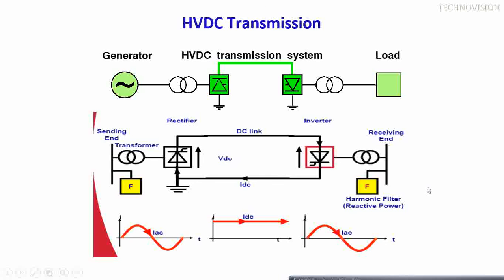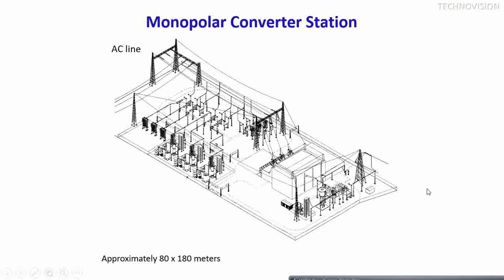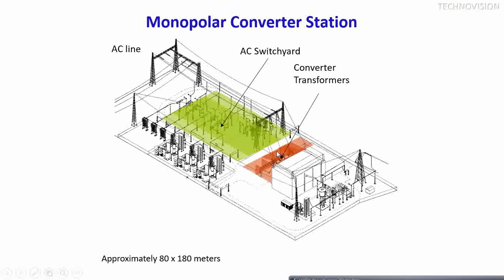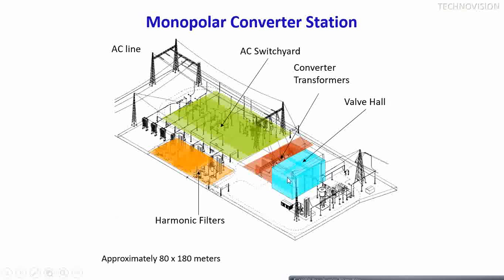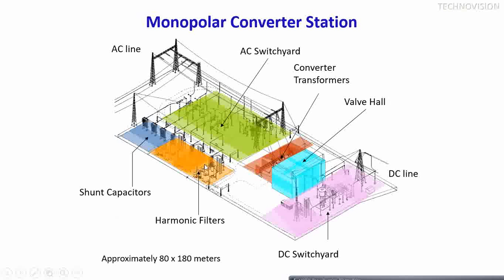A typical monopole converter station has an AC switchyard, converter transformers, and thyristor valves — an indoor structure where valves are suspended or hanging from the ceiling. In recent projects outdoor valves are used, placed on the ground. Harmonic filters and shunt capacitors are provided for additional reactive power supply.